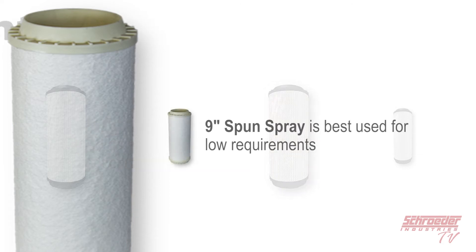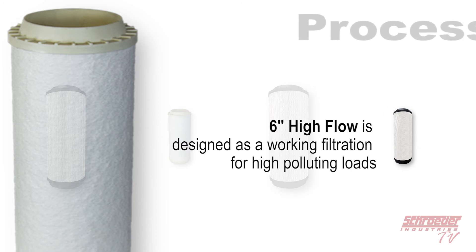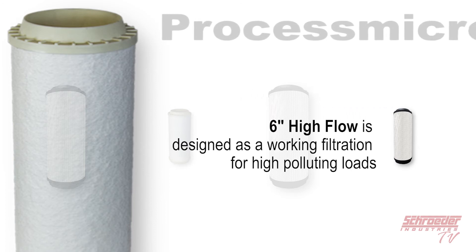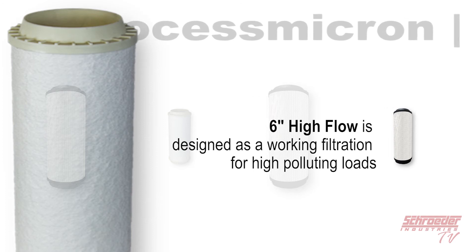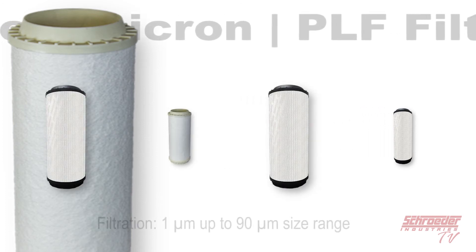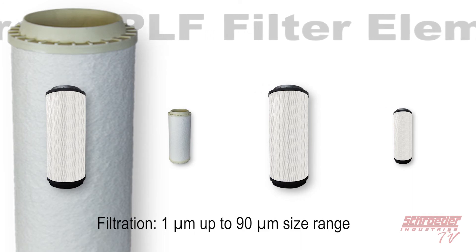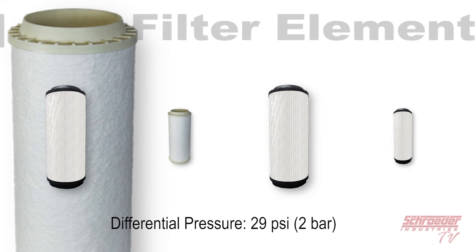The 9-inch spun spray filter element option is best used for low requirements, for example part cleaning. The 6-inch high flow filter option is designed as a working filtration for high polluting loads and is made with our M-Pleet material. All mentioned filter elements are micron rated for contaminants in the 1 micron up to 90 micron size range with a permitted differential pressure rating of 29 psi.